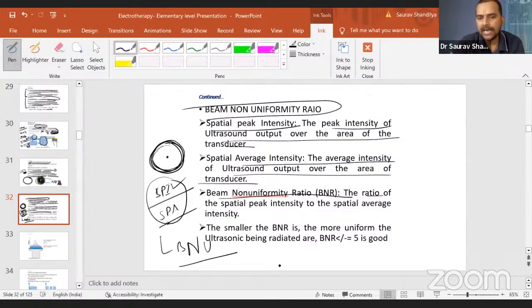If you have a smaller BNU, that means the spatial peak intensity stays closer to the average intensity. I mean spatial peak intensity divided by spatial average intensity, SAI. If this ratio is less than 5 or maybe equal to 5, then it is supposed to be a good ultrasound head. Why? Because it is not diverging; a more uniform wave is coming.